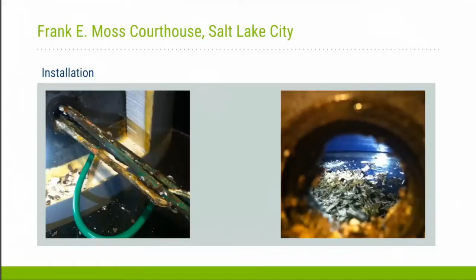Before we replaced or put in the device, you can see what the elements looked like as they were coming out. The elements were actually bending and opening up because of the heat. My mechanics would use a little hook to pull everything together; otherwise they weren't even able to get them out of the tank.